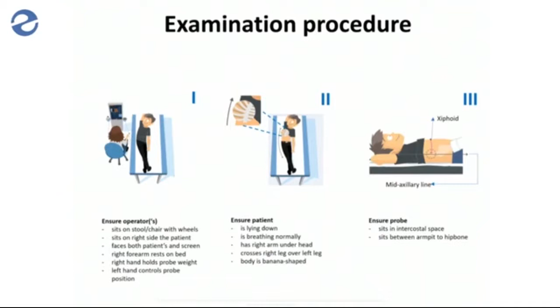Now, if you want to go for a probe, it's pretty important, as Patrick said already, that you have 3 probes. There are actually criteria for each single probe, which are based on the thoracic perimeter of the patient for the S probe, and not BMI. I insist on that. BMI is not a good criterion to select between M and XL probe.